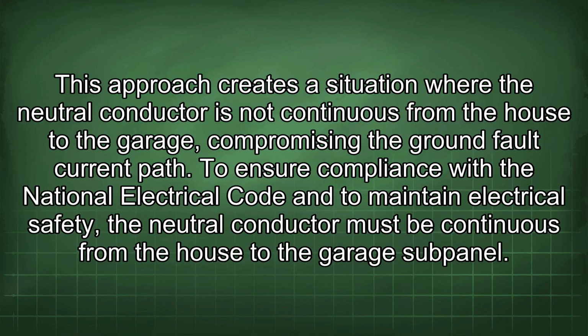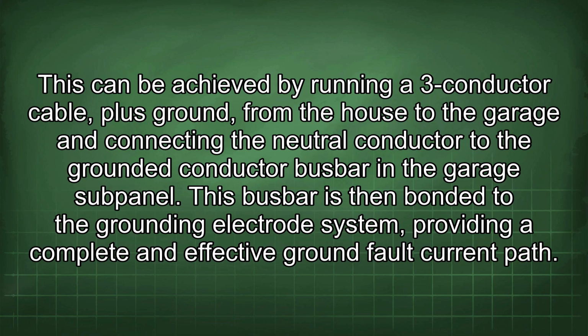This approach creates a situation where the neutral conductor is not continuous from the house to the garage, compromising the ground fault current path. To ensure compliance with the National Electrical Code and to maintain electrical safety, the neutral conductor must be continuous from the house to the garage subpanel. This can be achieved by running a 3-conductor cable plus ground from the house to the garage and connecting the neutral conductor to the grounded conductor busbar in the garage subpanel. This busbar is then bonded to the grounding electrode system, providing a complete and effective ground fault current path.